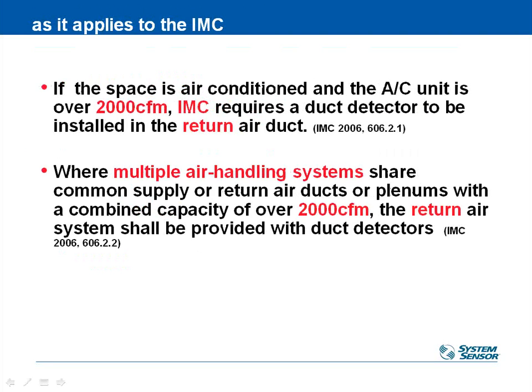International Mechanical Code, or as I'm going to call it, IMC, also requires that if you have over 2,000 CFM, same as NFPA, both look at 2,000 CFM, then you have to have a duct detector. The difference here is that IMC requires it in the return air duct. NFPA requires it in the supply air duct. So that's the distinction.